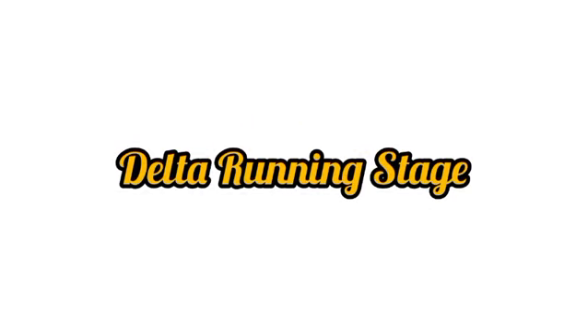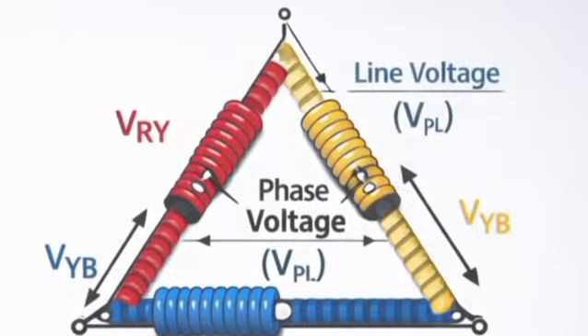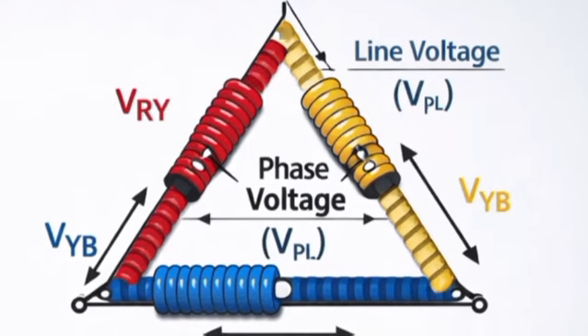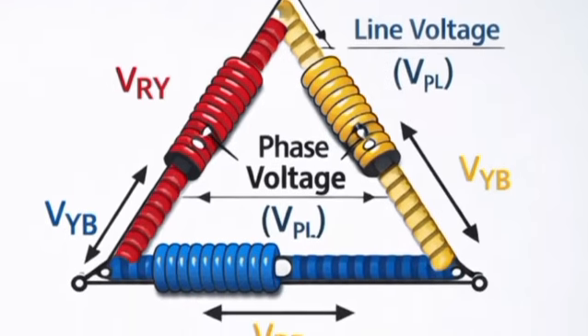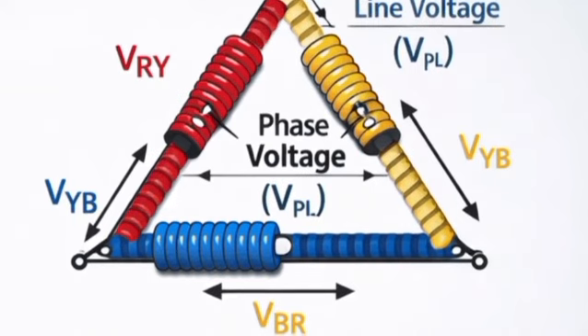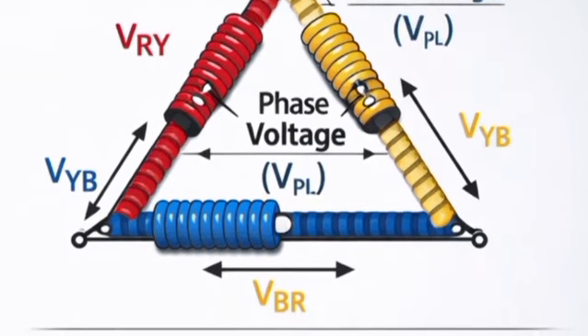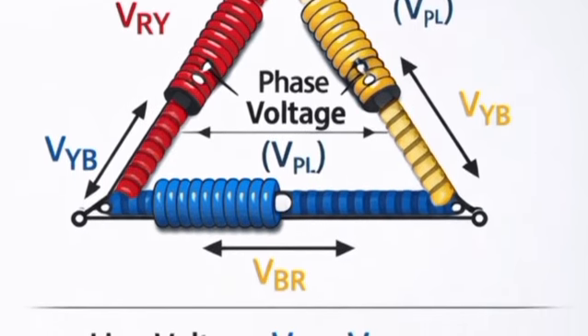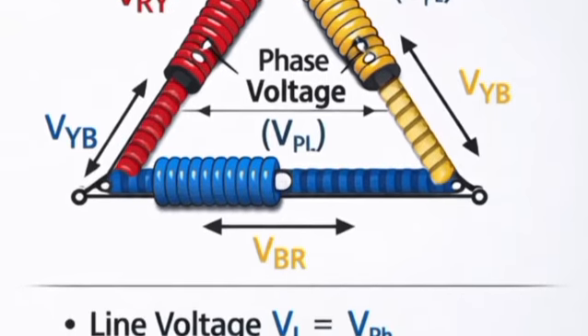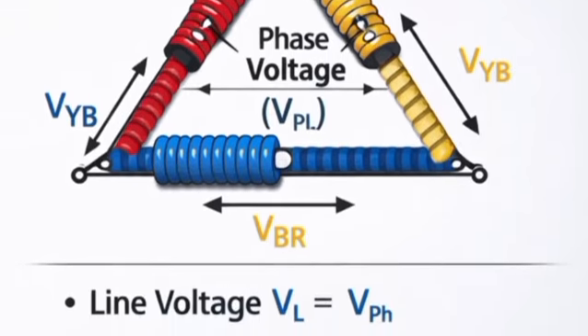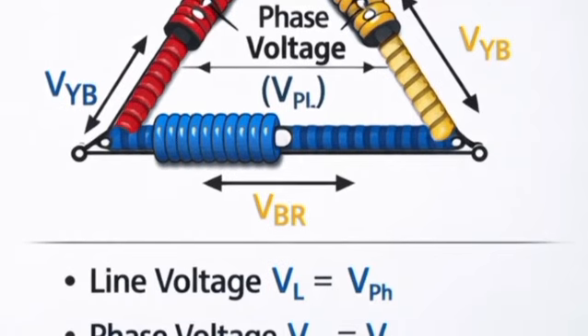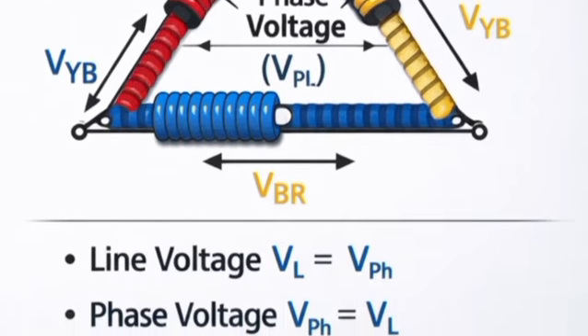Delta running stage. After switching to delta, the motor receives full line voltage. Now it delivers rated torque and operates normally under load. This final phase completes the function of the star-delta starter. The motor continues running in delta mode until it is stopped.